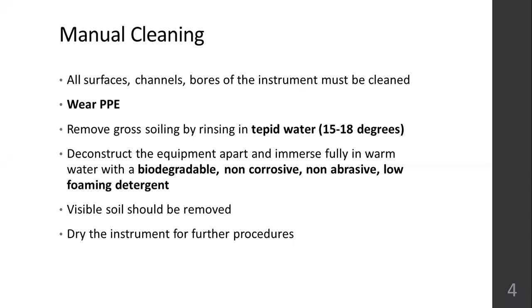If there are any equipments which require deconstruction, remove it part by part and immerse all those parts fully in warm water which has a biodegradable, non-corrosive, non-abrasive detergent. Detergent should be used in the water, but it should not corrode or be abrasive on this equipment. All the visible soil should be removed. And dry all the parts, dry the instruments before you send them for further processing. That is manual cleaning. It takes time.